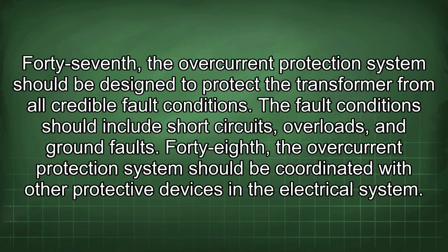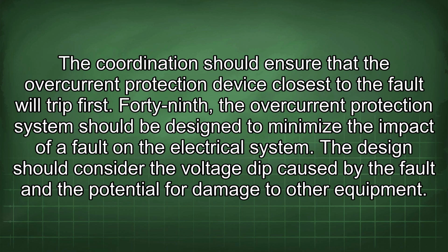47. The overcurrent protection system should be designed to protect the transformer from all credible fault conditions. The fault conditions should include short circuits, overloads, and ground faults. 48. The overcurrent protection system should be coordinated with other protective devices in the electrical system. The coordination should ensure that the overcurrent protection device closest to the fault will trip first.